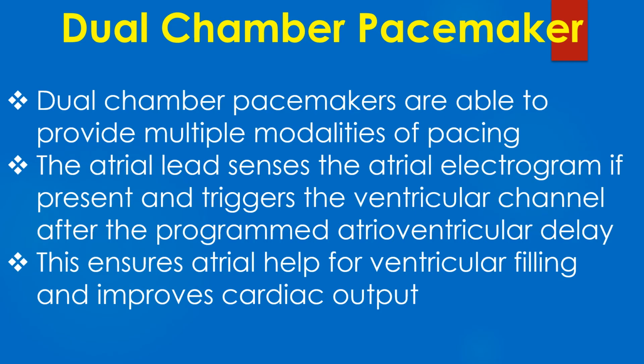Dual chamber pacemakers are able to provide multiple modalities of pacing. The atrial lead senses the atrial electrogram if present and triggers the ventricular channel after the programmed atrioventricular delay. This ensures atrial contribution for ventricular filling and improves cardiac output.